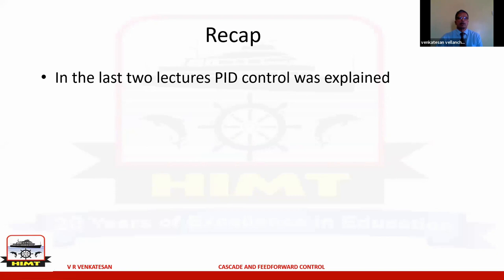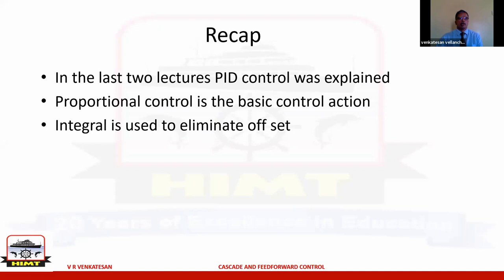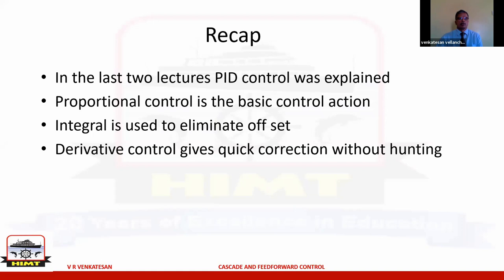To recap what we have already covered in the previous lectures: PID control was covered — proportional, integral, and derivative control, and combinations such as proportional plus integral and proportional plus derivative. Proportional control is the basic control action, integral control is used to eliminate offset, and derivative control gives a quick correction without hunting. P plus I is the most common type, used in around 70-75 percent of process control applications, with only another 20 percent requiring derivative.